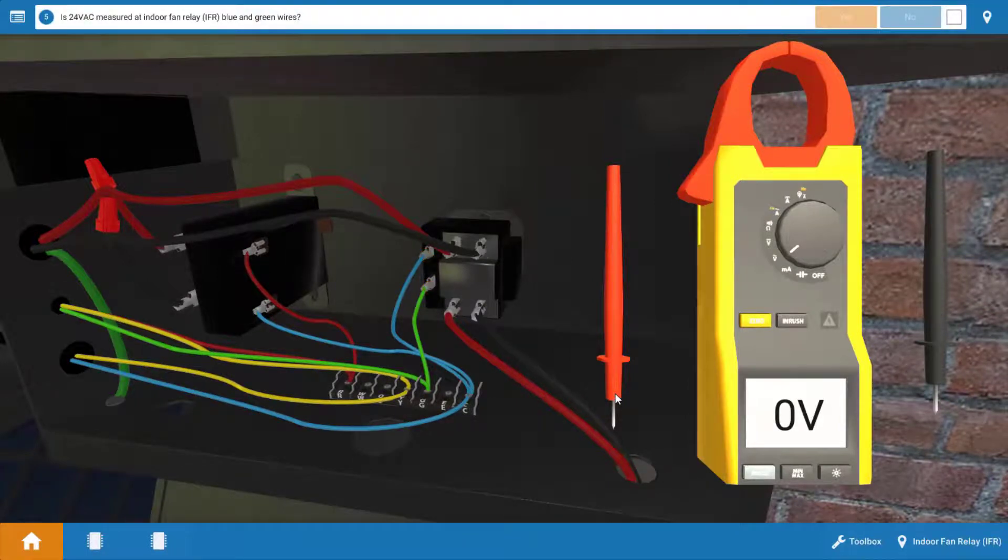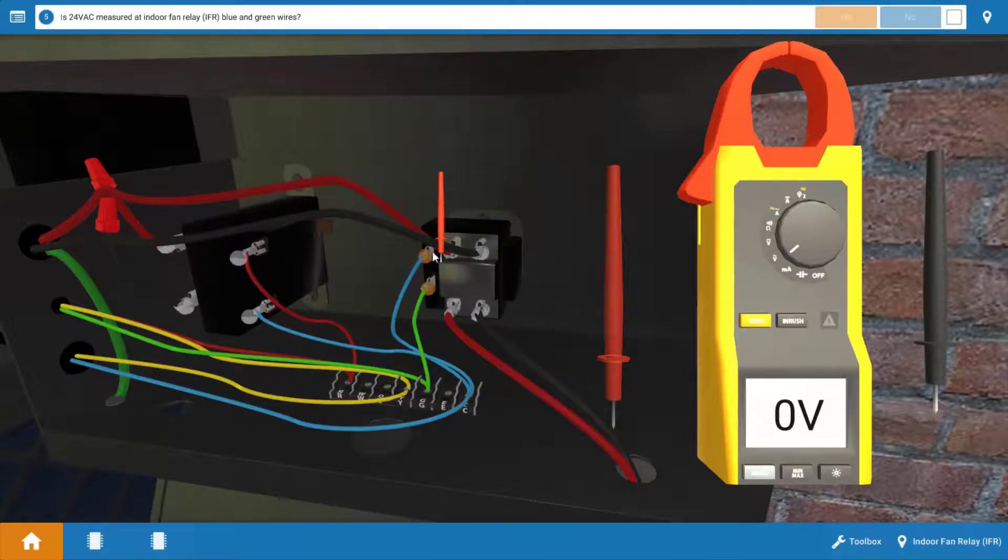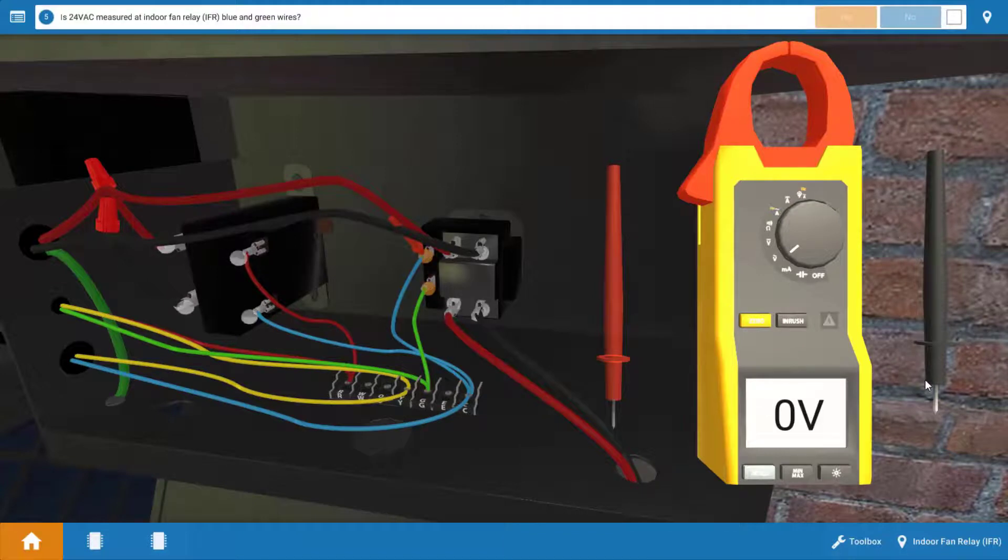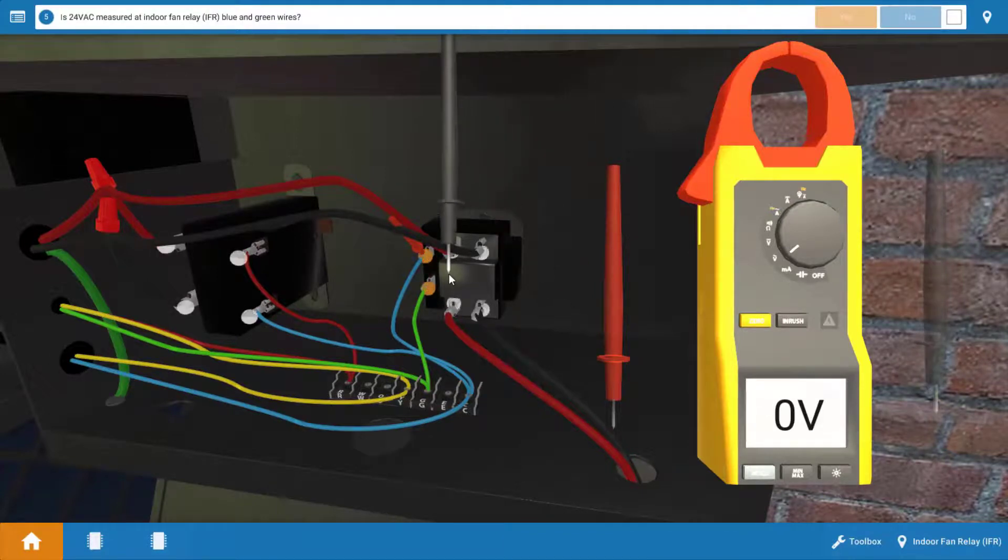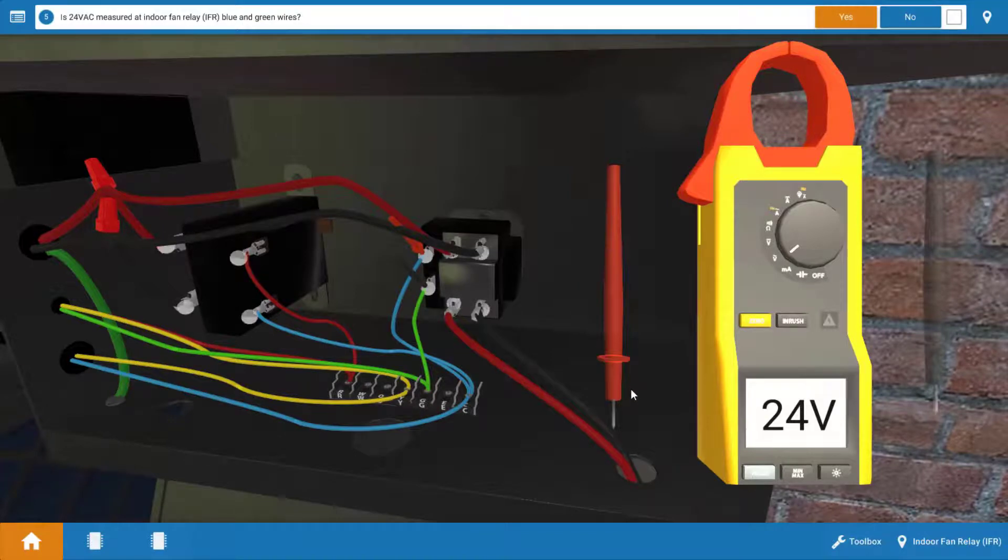And again, you can review the wiring diagram if you want to look at the color codes. So drop the leads on the coil and see if we're getting 24 volts from the thermostat to the coil. And when we do that, yes, we are. We have 24 volts.